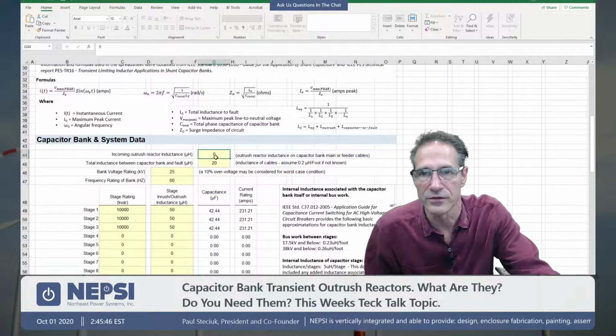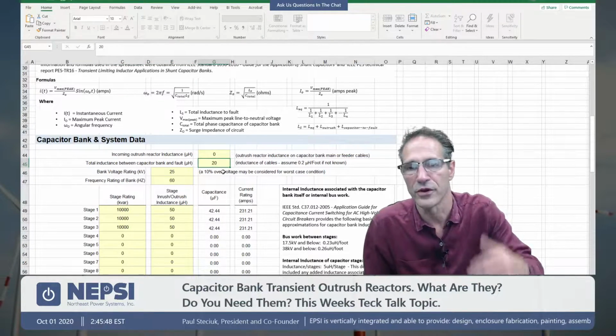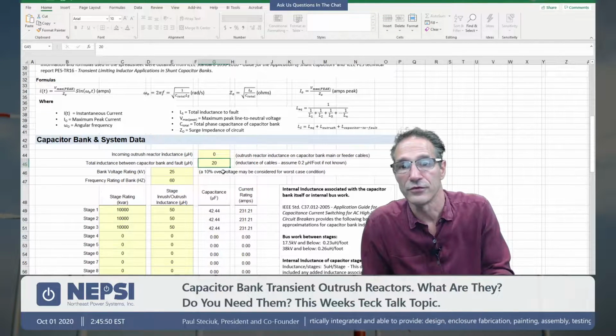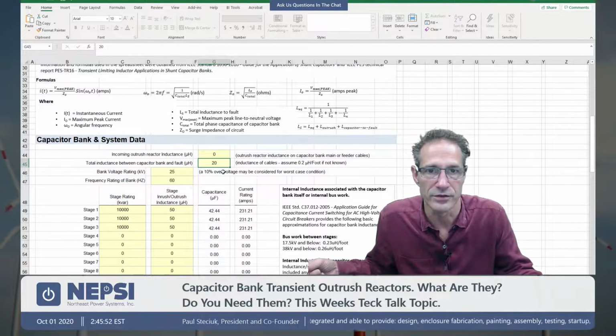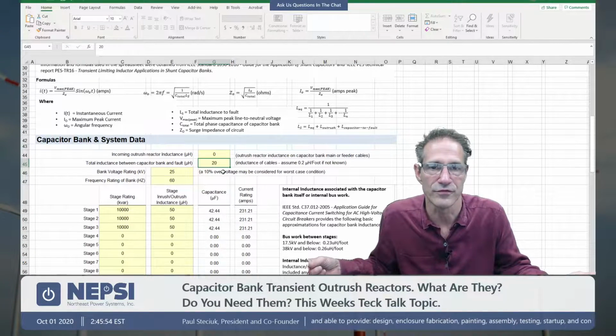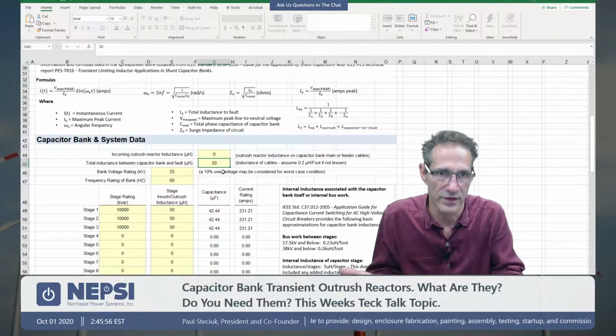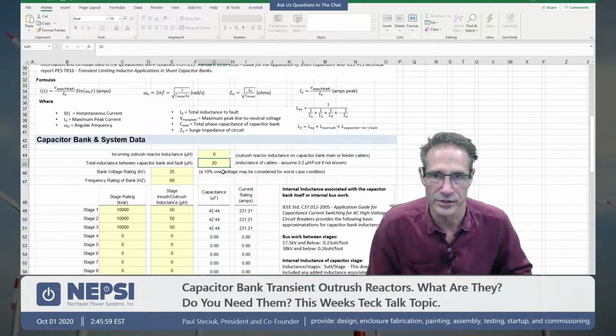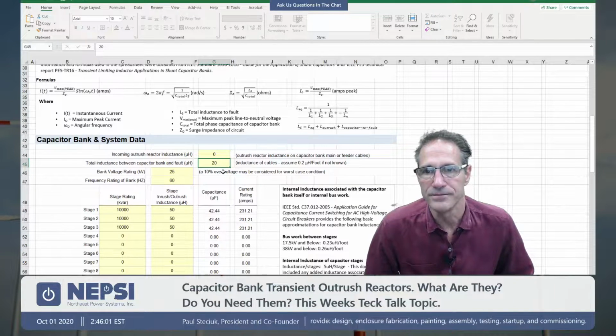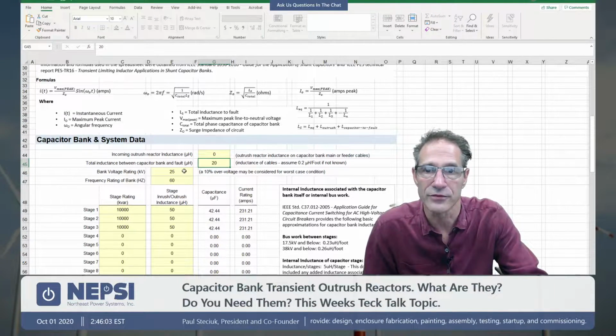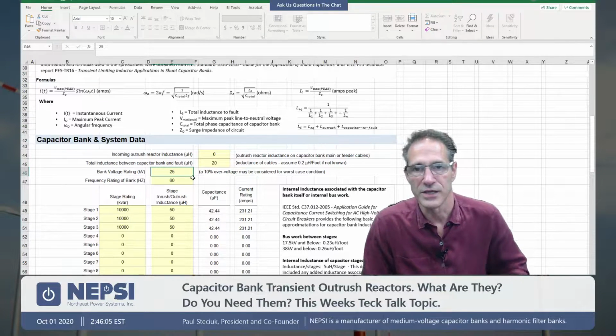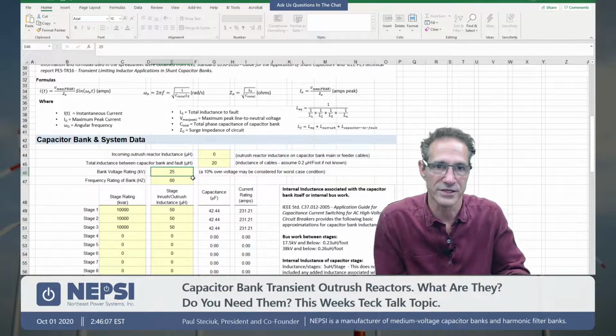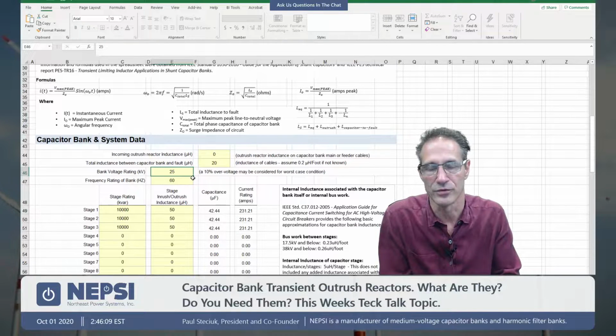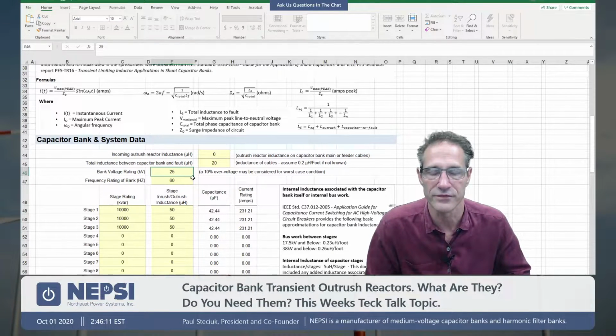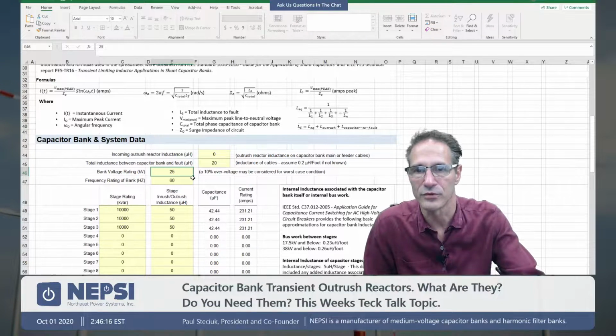You put in your values of microhenries for your outrush reactor, for the incoming cables, assume about, in this case, we're saying 0.2 microhenries per foot. So I mentioned 0.5, the value is 0.2. My memory is going as I age. You also have to put in your capacitor bank voltage. It does change the outrush value. Do the calculation at the peak voltage, not at the normal system voltage, because at peak voltage you will have a higher output. So do it at peak voltage rather than nominal voltage.